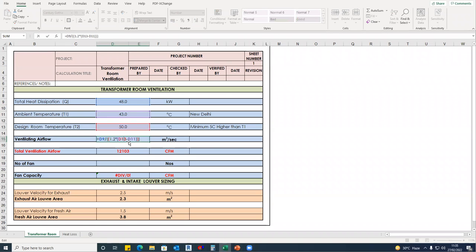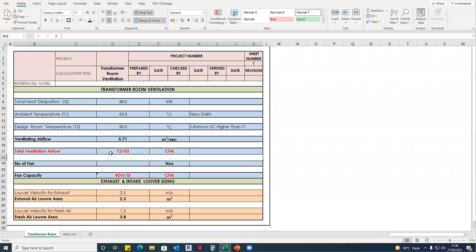Now ventilating airflow has a formula. Okay, you can check the details of this formula in the DG room ventilation video. Then total ventilating airflow is 12,103 CFM. Okay, I have just converted this into CFM. That's it, nothing else. Conversion factor is 2118. Number of fans, I'll use one fan. And the CFM I'm getting is 12,103 CFM for the transformer room.